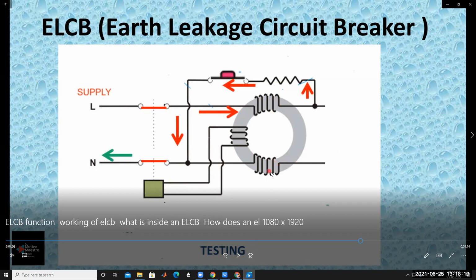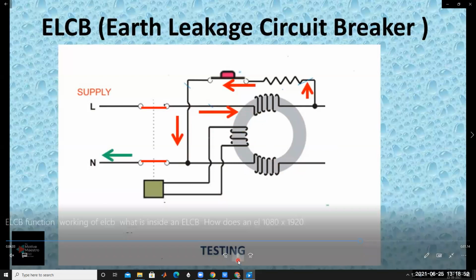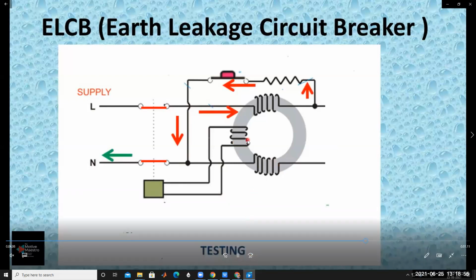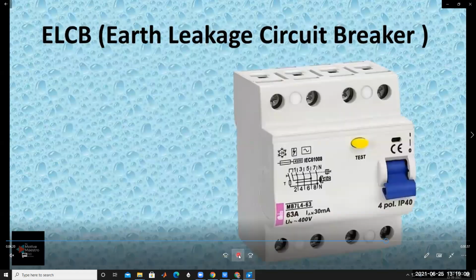Because of this, no flux is developed in it. This coil is open circuited, so there is no use of it. If it were a closed circuit, then only it would be used, but it is open circuit, so no current flows through this coil. Then only the flux due to coil 1 is developed, and the flux links like this. Whatever flux is generated, the sensing coil senses it, and then the trip relay operates. It's clear. So because of coil 1 only, magnetic flux is developed, and because of this magnetic flux, the sensing coil senses it and the trip coil is activated. In this way, this ELCB is tested.